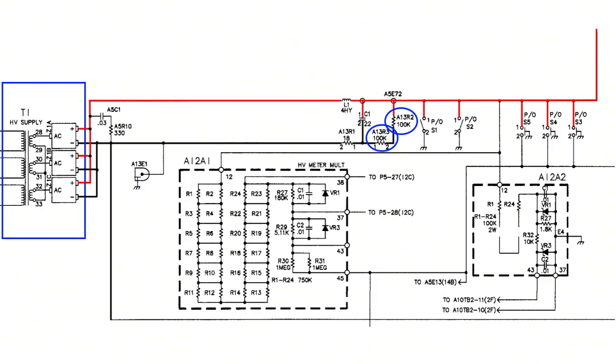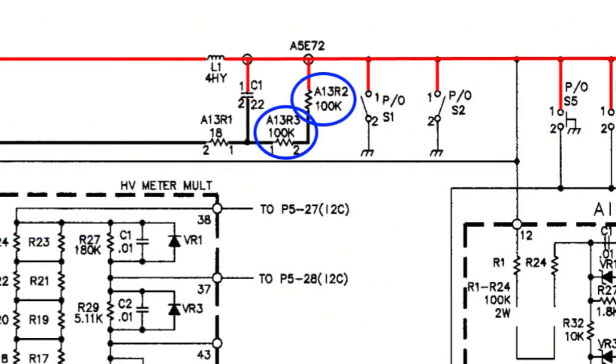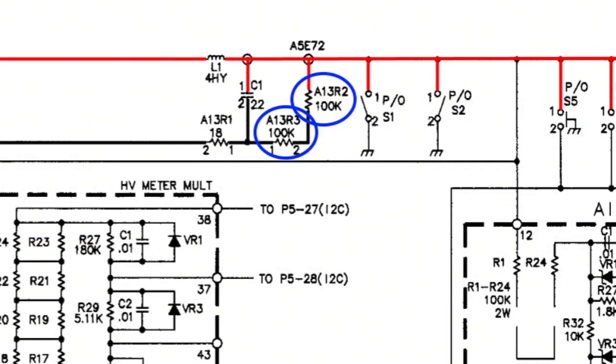It's a 22 microfarad. That's not very big. Well, actually, this capacitor is about 18 inches tall and about that deep and about 4 inches wide. When you're putting 10,000 volts on it, a 22 microfarad capacitor can get pretty large. That's the filtering on that power supply. To take the ripple off, that thing will hold quite a punch. So those two 100k ohms in series there, what that does is it's always putting some load across that capacitor. So when you turn off the high voltage, that capacitor's still got a heck of a charge on it. Those are responsible for bleeding it on down and preventing you from getting a nasty shock. But those things will open up and you won't have anything across that.